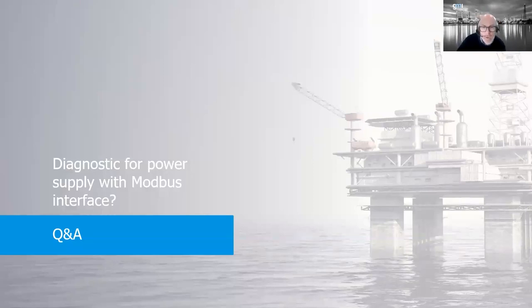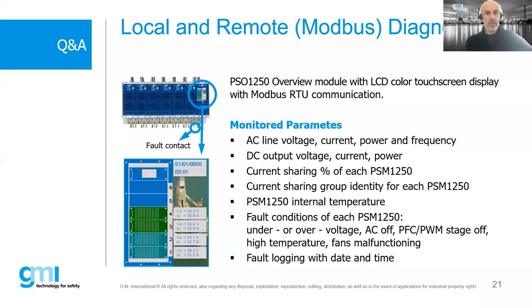Well, some words about the diagnostic and Modbus with our power supply system. We do have this possibility, an option with a display that shows all the information regarding all the power supply modules, like AC input current, power and frequency, DC output voltage, current, power, current sharing for each module, internal temperature, fault condition. Everything is continuously monitored by the display, and also, of course, can be transferred to the PLC over Modbus RTU interface.